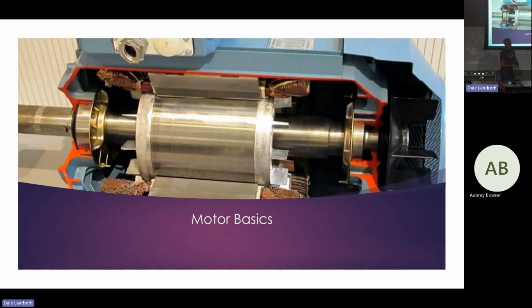So if you've got a motor and you look at the nameplate and the stator is usually 3,600 RPM, is that rotor actually turning 3,600 RPMs? No, it's not. Because there's a little slip, there's a little distance between what the stator's doing and what the rotor's doing. So the rotor is always trying to catch up to the stator, and it never will. But they do have synchronous motors -- we won't see them in our application -- synchronous motors run the same speed. So it's a little different. But that's what a motor is doing.